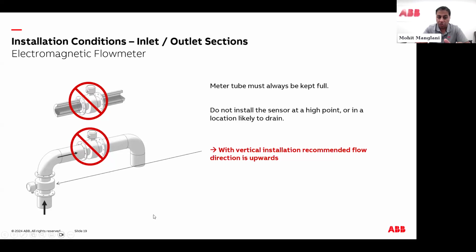First thing is, on an installation, your best installation is vertical up. You're going against gravity. The nice thing is, you're always guaranteed a full pipe when you have enough pressure going through the line. If you install it on the top of an elbow, that's a little bit of a challenge because then your line can drain and you may not know if you have a full pipe or not. So this is not recommended, but if you have an installation where you're coming down and then going back up, you'll always have enough back pressure to have a full pipe.